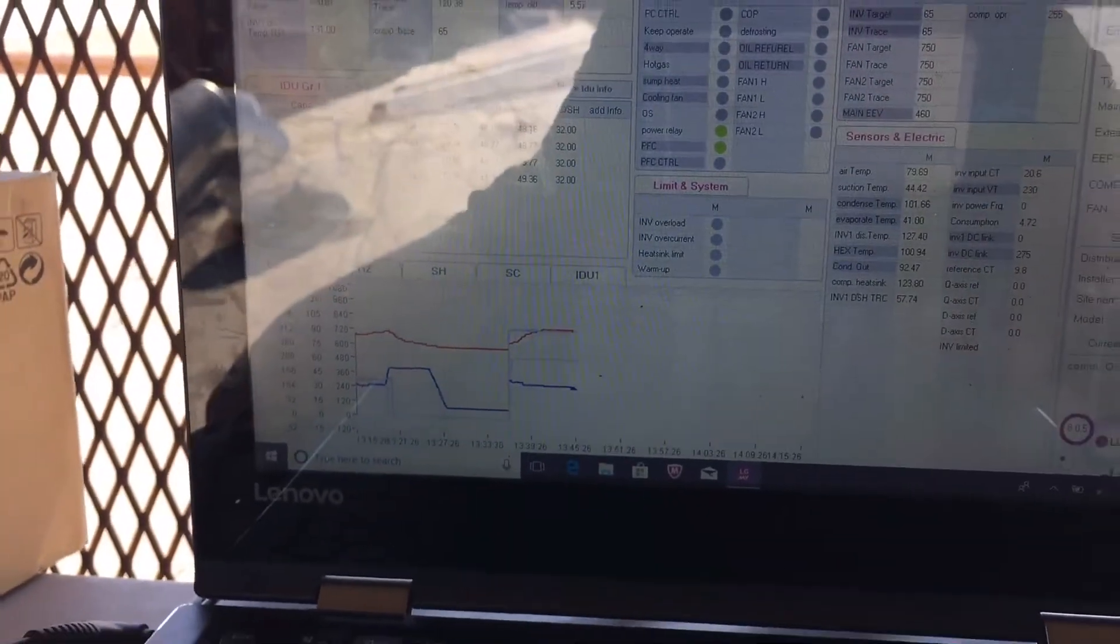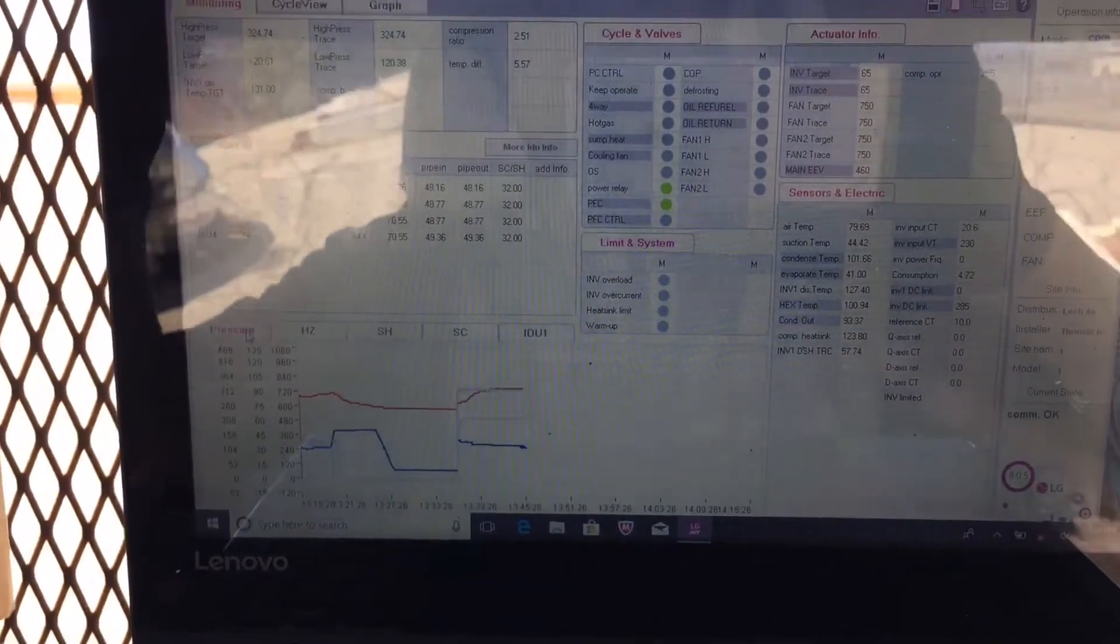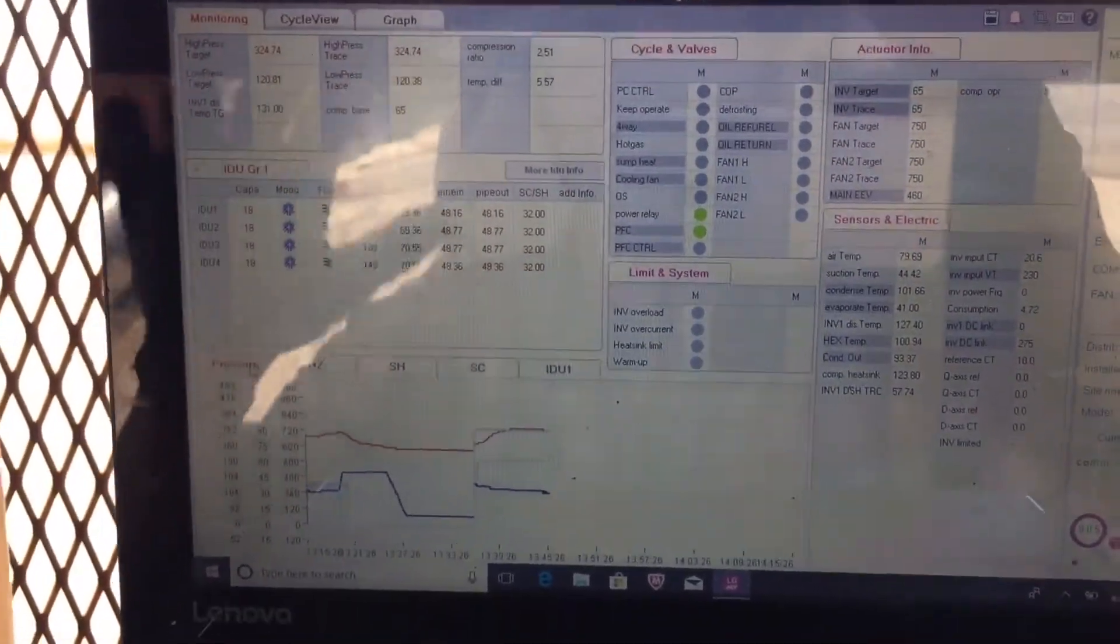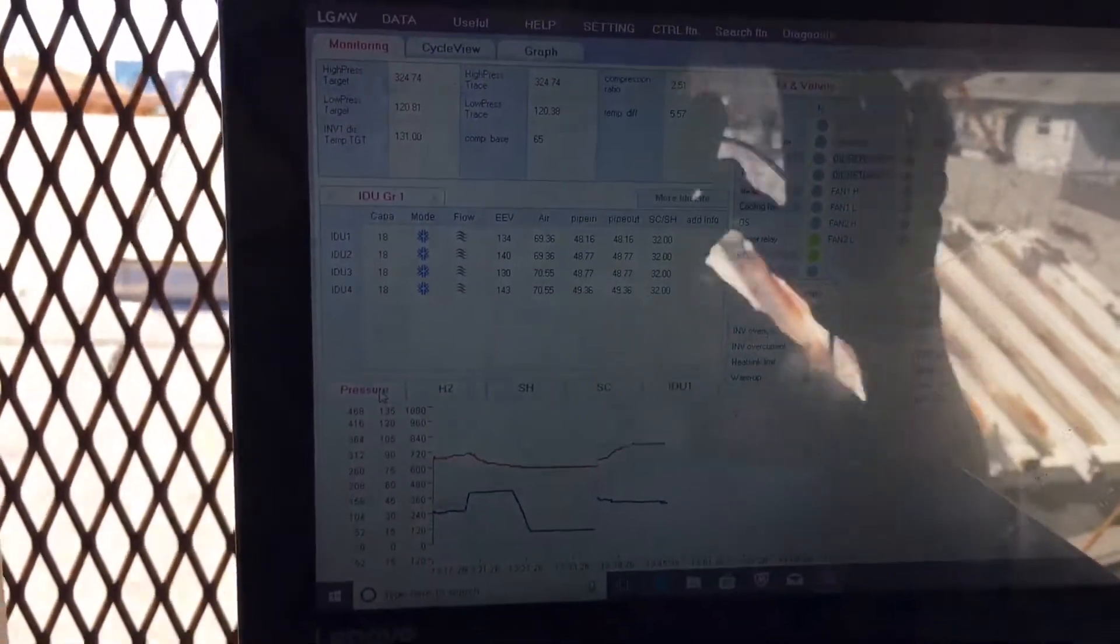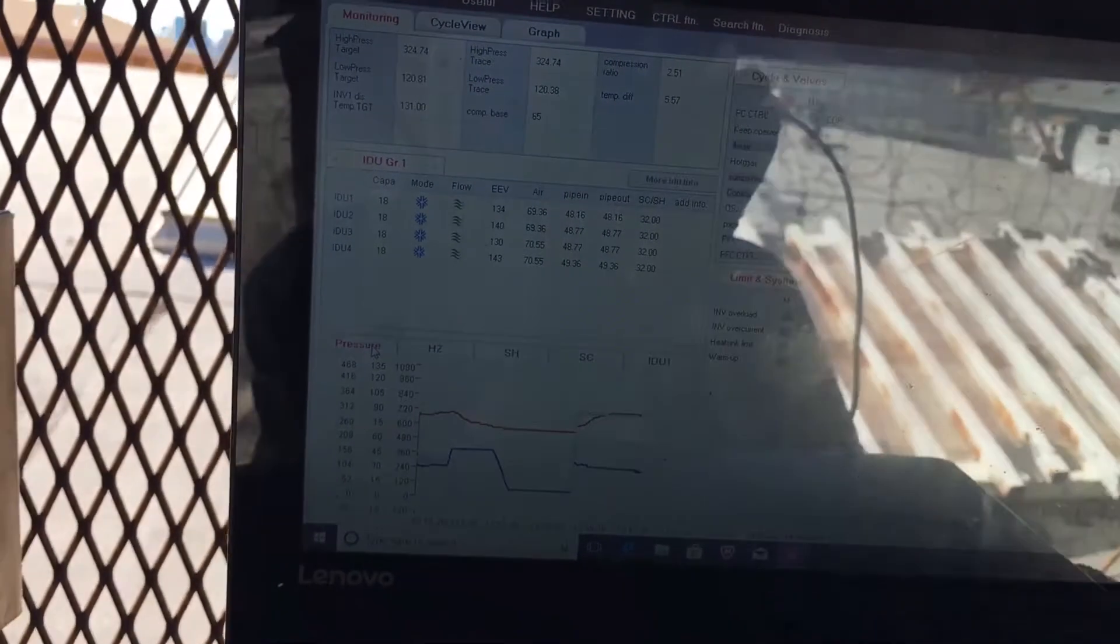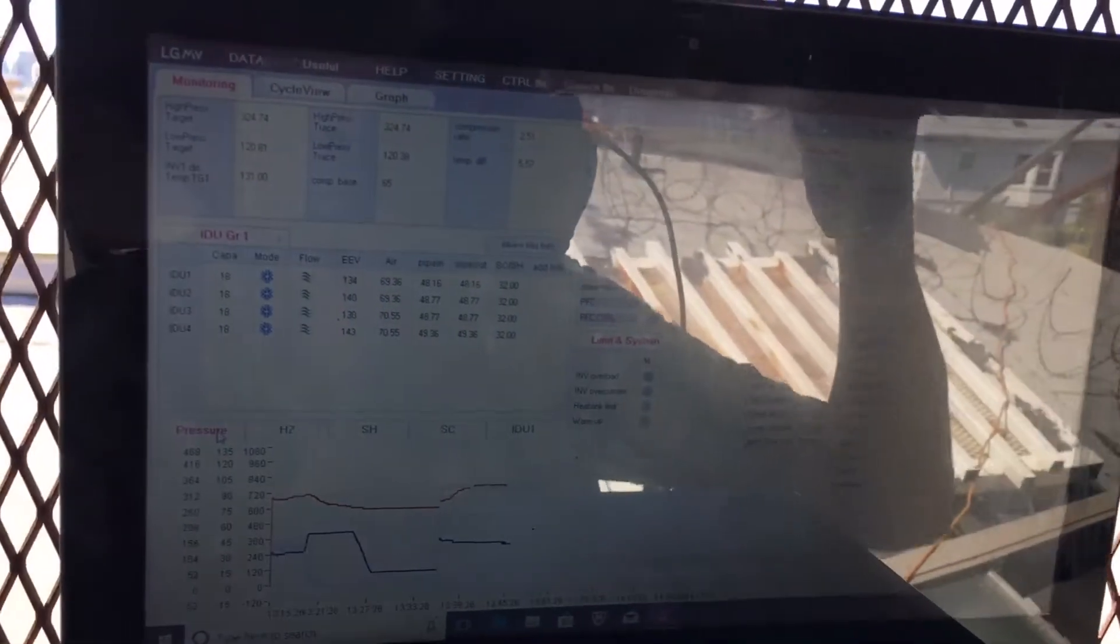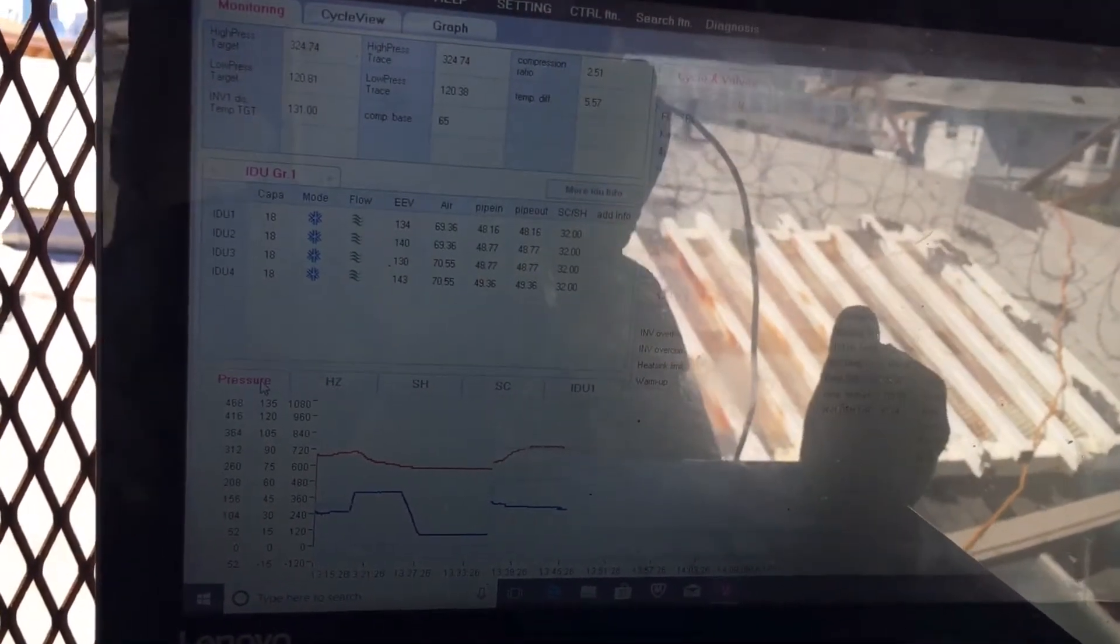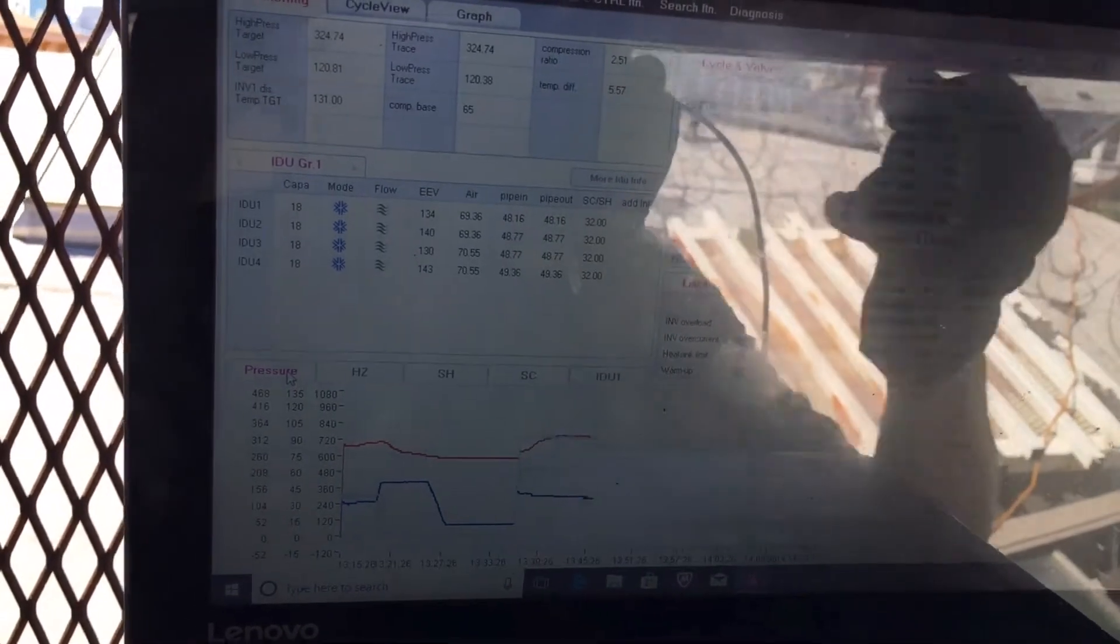Not just high, low, heat or cold on any given day. It's a different animal. So these guys who keep trying to go beer can cold and stuff a few pounds in a system and go, don't even go there. Drain the system all the way down, fill it all the way back up. Do not top off these systems.